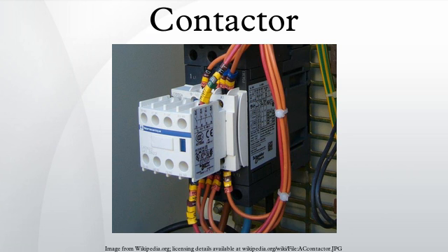When current passes through the electromagnet, a magnetic field is produced, which attracts the moving core of the contactor. The electromagnet coil draws more current initially, until its inductance increases when the metal core enters the coil. The moving contact is propelled by the moving core. The force developed by the electromagnet holds the moving and fixed contacts together. When the contactor coil is de-energized, gravity or a spring returns the electromagnet core to its initial position and opens the contacts.